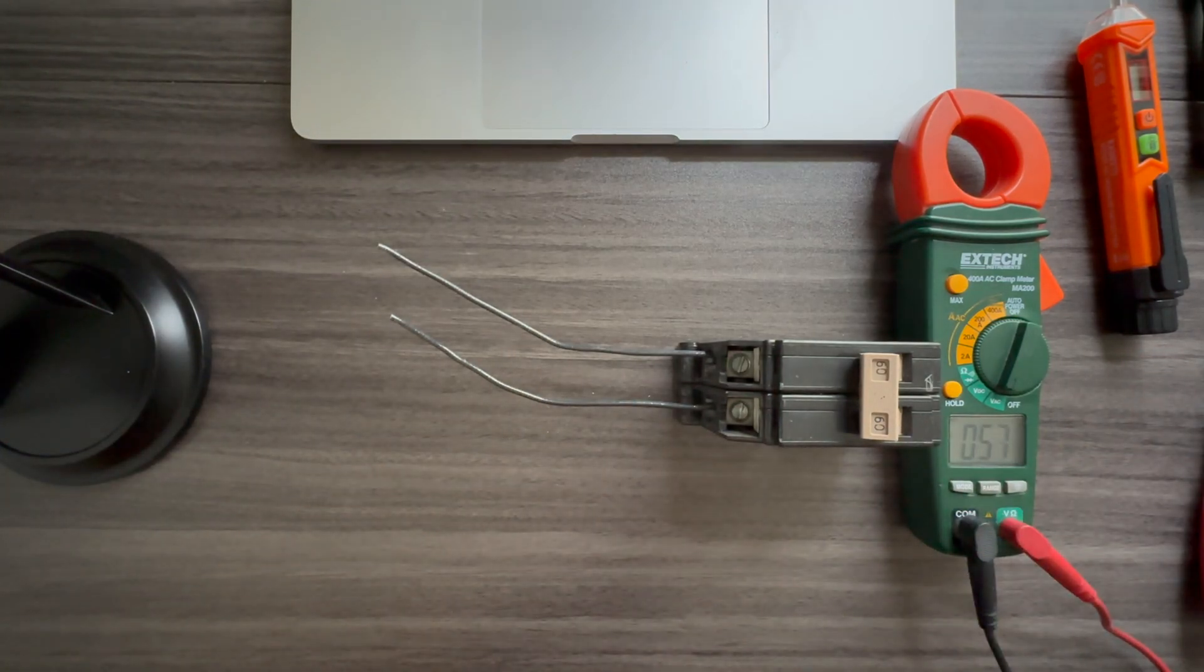If we don't, the breaker is bad. And then we're going to test each terminal. We're going to touch this, 125. We're going to touch this. We need to get 125 when we touch this one through any ground on the panel. So in that case, you know 100% if you have a voltage when it's turning on and it's reading, the breaker is all good.